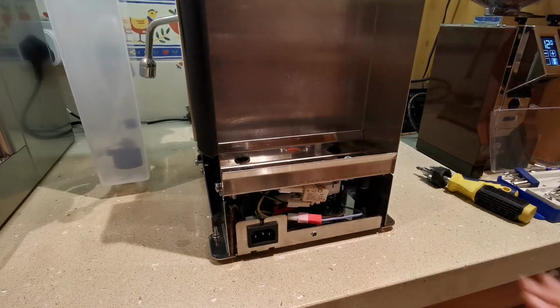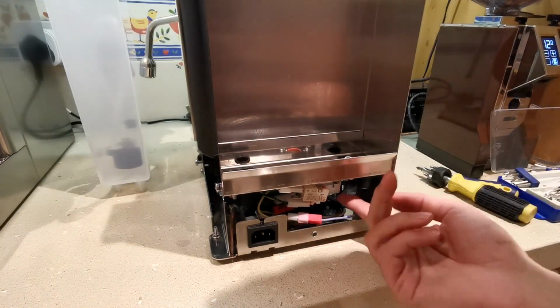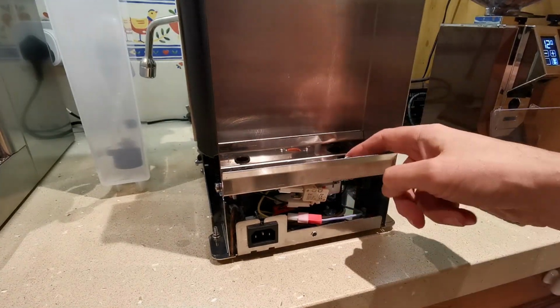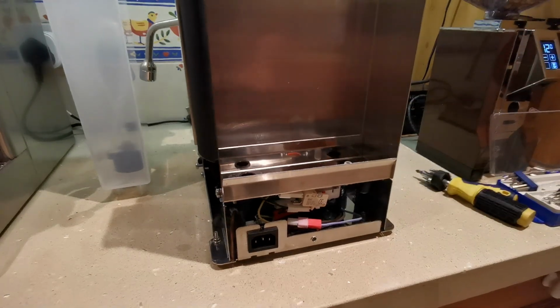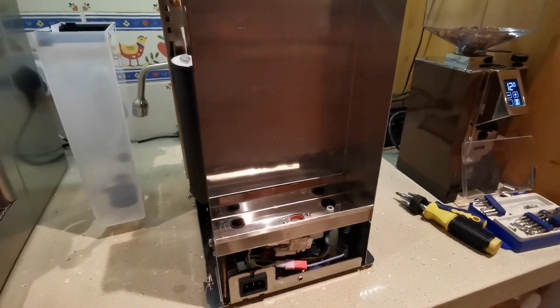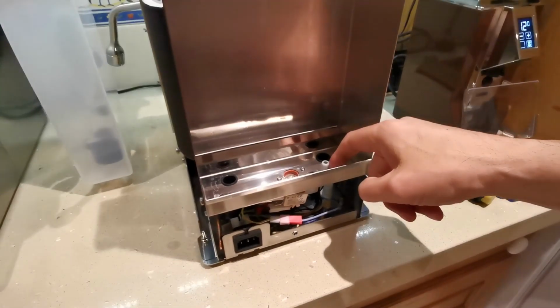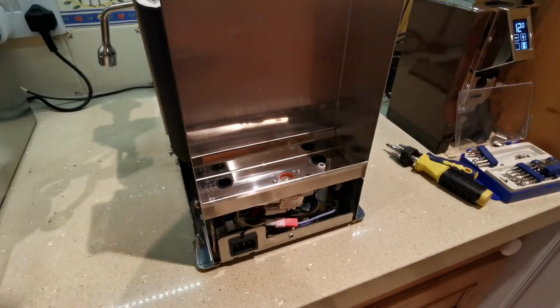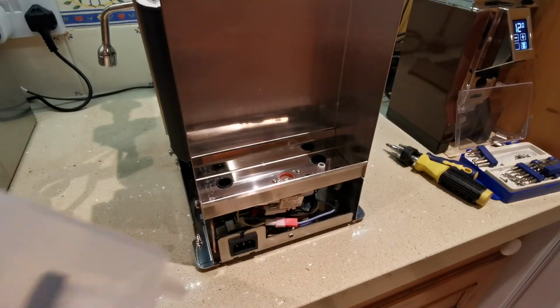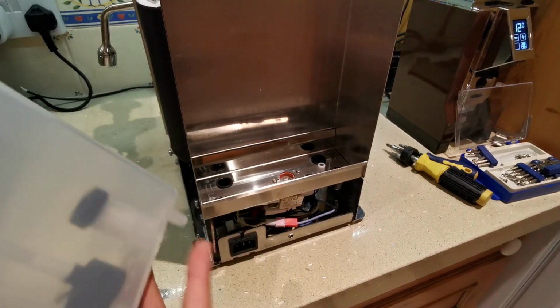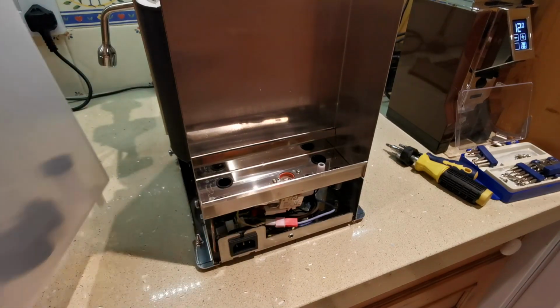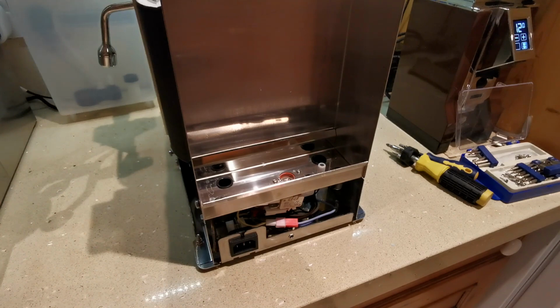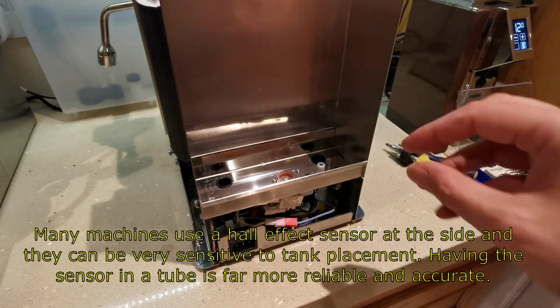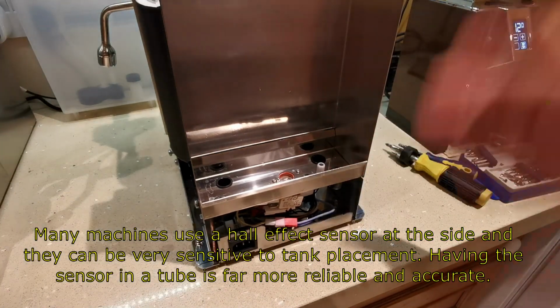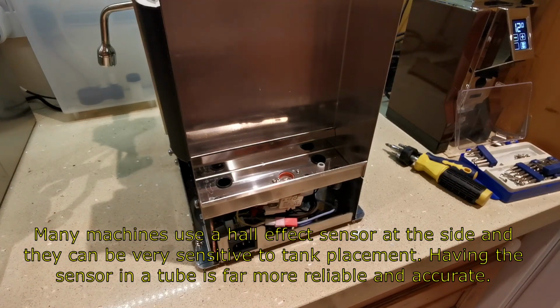Now here's a Hall effect sensor. That's got a couple of wires, a little Hall effect sensor here. Let's move up and have a look. And that Hall effect sensor goes inside a tube on the tank with a little float in it, and it's a very reliable method of water detection because it's centered exactly in the center of the float, and it gives good low water detection.